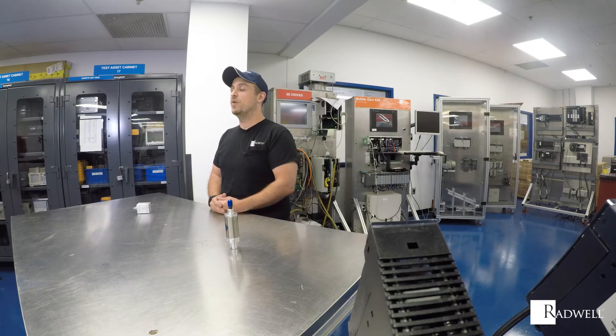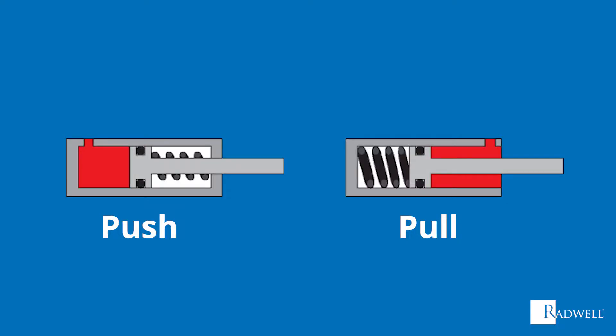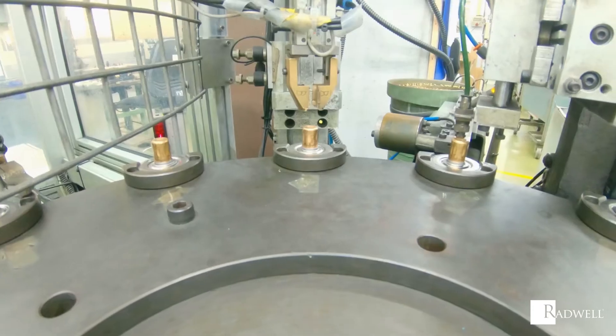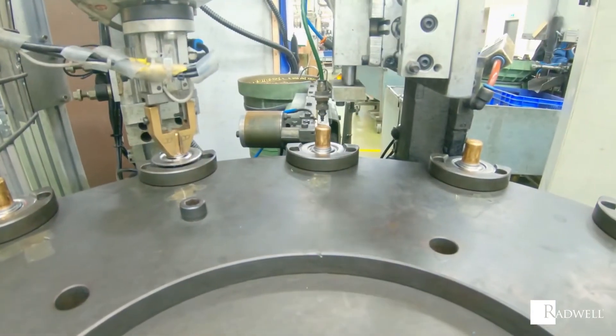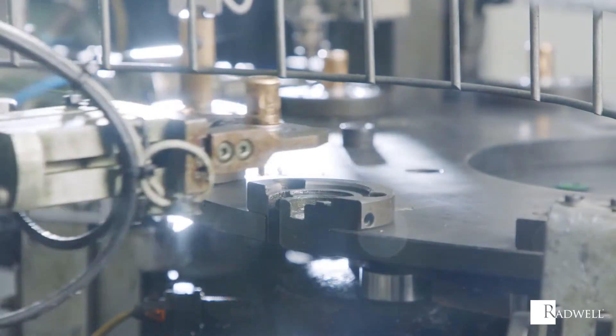The return stroke is accomplished by a spring, weight, mechanical movement, or gravity. There are two types of single acting cylinders: push and pull. For push, the pressurized force pushes the piston out of the cylinder; for pull, the pressurized force pulls the piston back inside. Single acting cylinders are used for applications where clamping, positioning, pushing, pulling, and marking are needed.